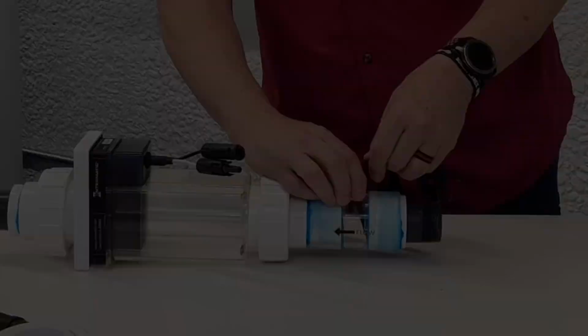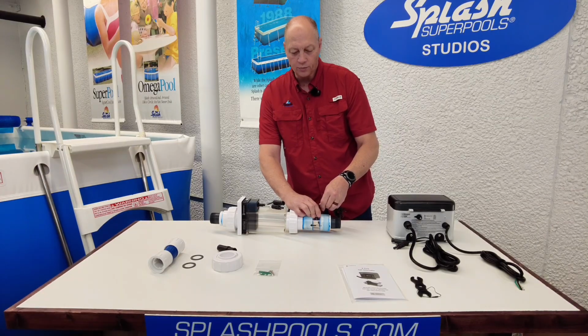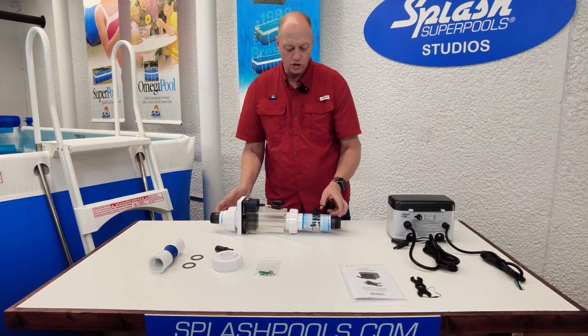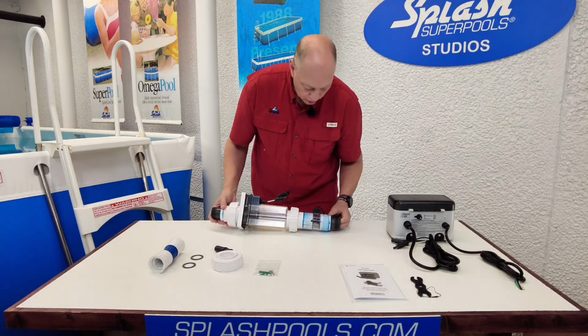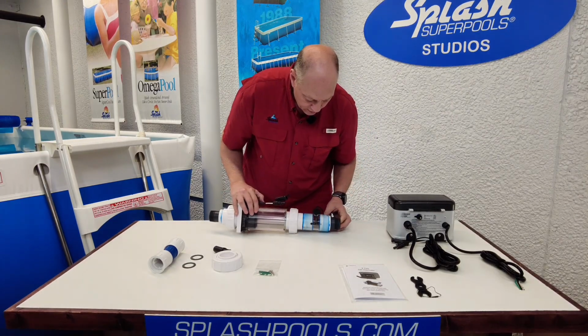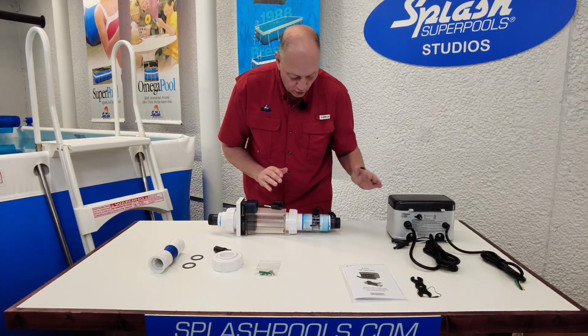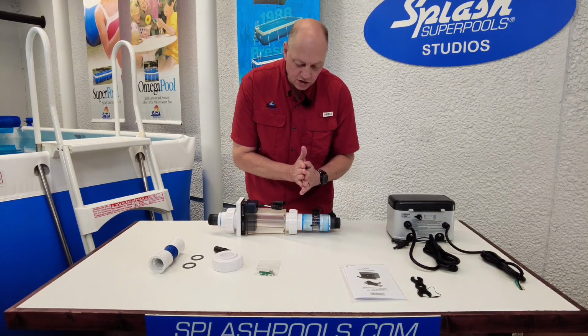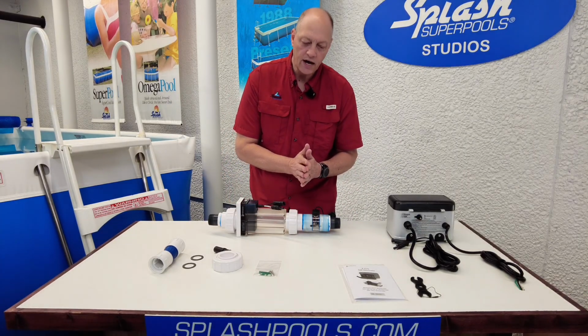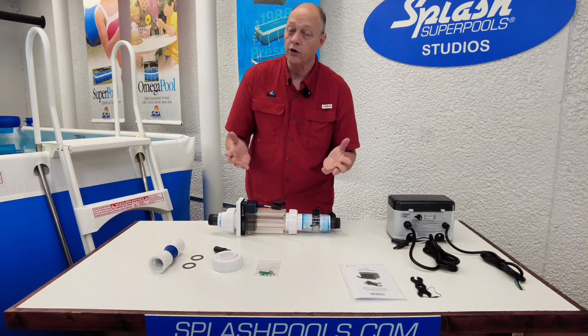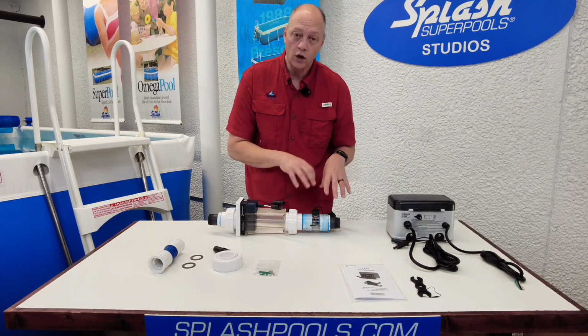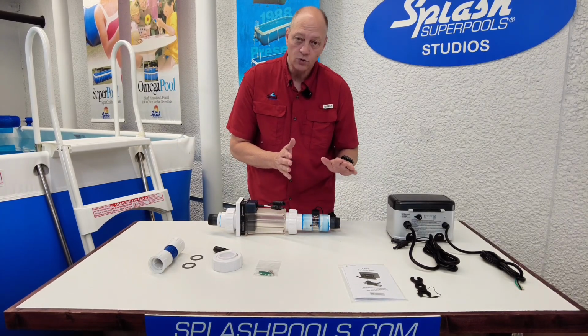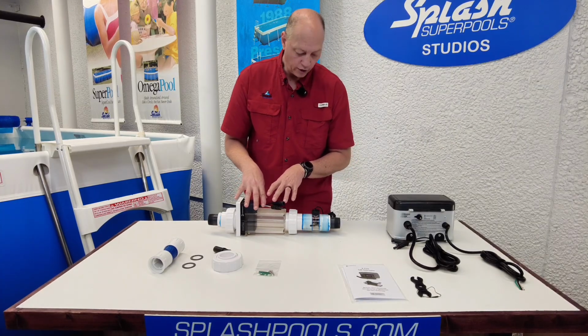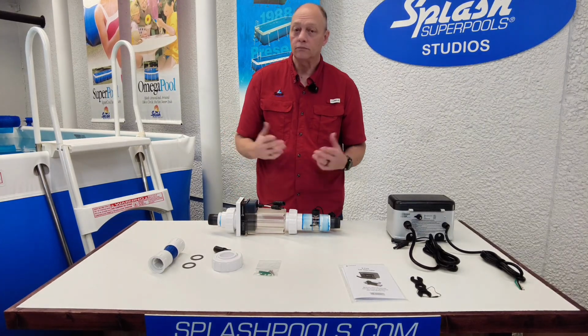Screw that cap down, tighten it up. It's got an O-ring to help it seal, so again, you don't have to just wrench down on it. You'll be able to look in there and see that when the water is flowing, the paddle is going to push up against the stick. Once it makes contact, it allows the system to make chlorine. It's a great safety feature because if the flow of the water stops, the paddle comes away from it, and it doesn't generate chlorine. So we've got our flow switch in. Let's go to the next step.